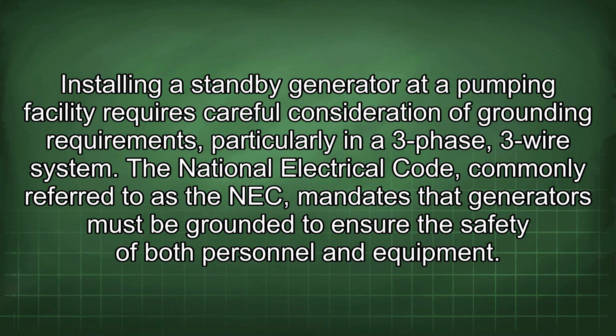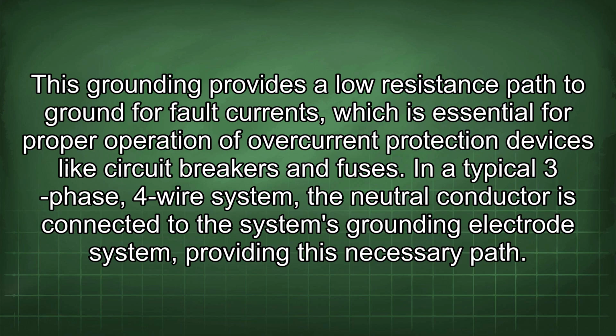Installing a standby generator at a pumping facility requires careful consideration of grounding requirements, particularly in a three-phase, three-wire system. The National Electrical Code, commonly referred to as the NEC, mandates that generators must be grounded to ensure the safety of both personnel and equipment. This grounding provides a low-resistance path to ground for fault currents, which is essential for proper operation of overcurrent protection devices like circuit breakers and fuses.